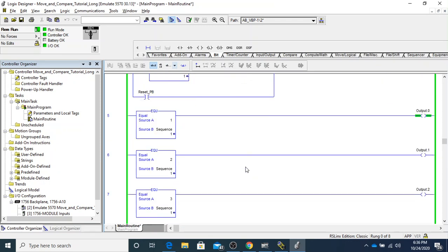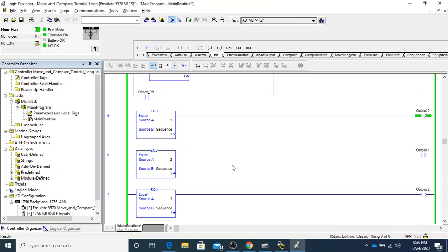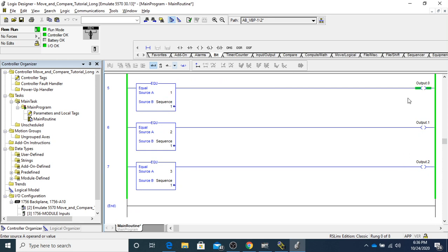So here we are going back through the motions. We're using the pulse timer now. So now we have a reset, so no matter where we're at in our cycle, let's just say a machine was to get a jam and you had to stop the machine and clear the jam and you needed to reset it back to its first cycle, you could. You could even do it with a start button. So as soon as you push the start button, it automatically starts back, so anytime the machine was restarted, you don't have to do a reset. You could do a start button. You can do multiple things to get it to a zero state. So it always starts out at the first part of the sequence on a machine or an application or a process. Okay, but as you can see, it's going all through.